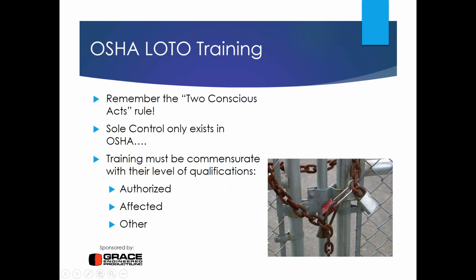Now, in terms of some basic concepts, one of the primary ones I'd like you to know is called the Two Conscious Act rule. The Two Conscious Act rule doesn't appear in the actual standard itself, but it is the basis upon which the entire lockout, tagout standards are built. The Two Conscious Act rule simply says this: in order to release energy, you're going to need to do two things purposefully, or on purpose, and one of those two things must require excessive force.